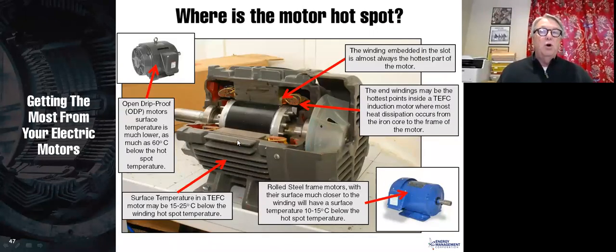So if you have an open drip proof motor and you feel the open drip proof motor, I've had a rule of thumb for a long time that if you can keep your hand on the outside of a motor for 3 seconds, it's not too hot. That doesn't really work so well for open drip proof motors because the air is going right through the motor, and the outside of the enclosure can be as much as 60 degrees centigrade lower than the inside. By the way, this data that I'm giving you came from ESA.